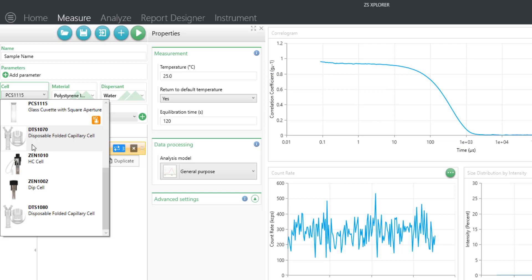The disadvantage of possibly using a disposable folded capillary cell for a sizing measurement, you would like to make sure the sample is optically clear. If not, and you're using a sample that's slightly opaque, you would get much better quality data in one of the other sizing cells.